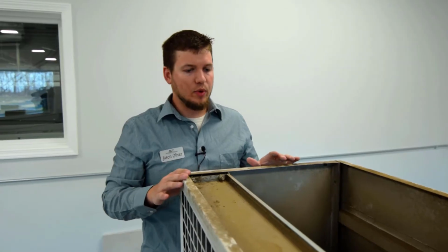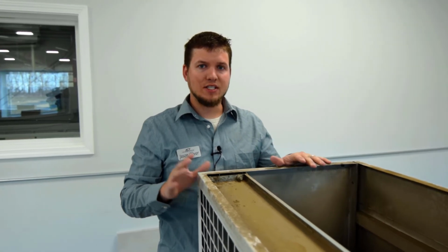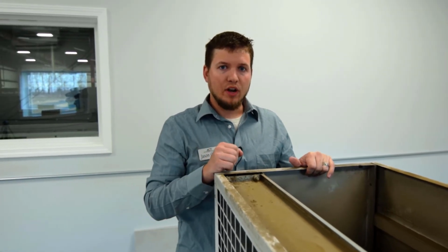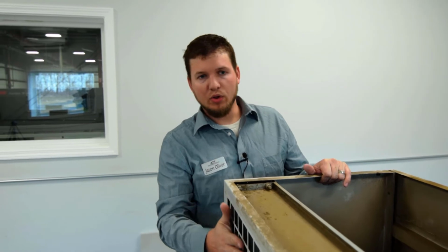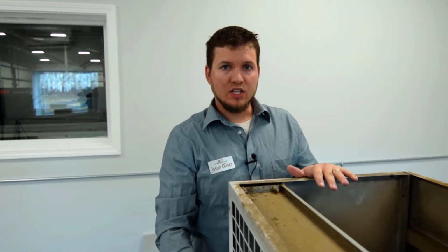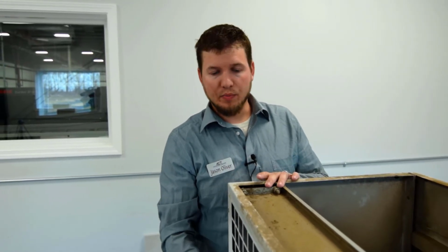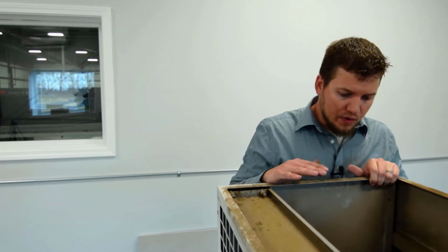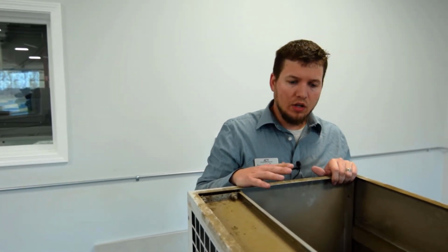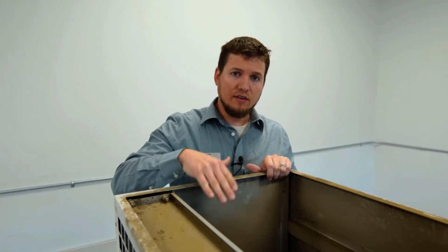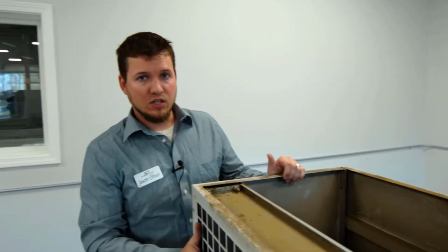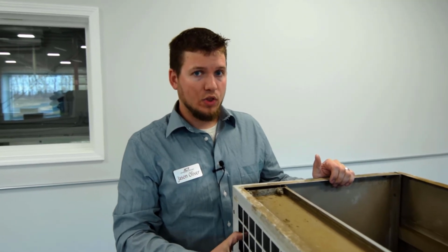Here at ACT, we require you to clean the condenser coil from the inside out. That's extremely important, as we tend to see this all too often, where only the outside looks clean, but the inside is still dirty, and we have reduced capacity because of it. Also, once you've completed the cleaning of the condenser coil, it is extremely important, and it's a requirement that you take a picture of the inside face of the coil and the outside face of the coil, as these are required to be submitted with your PM checklist.